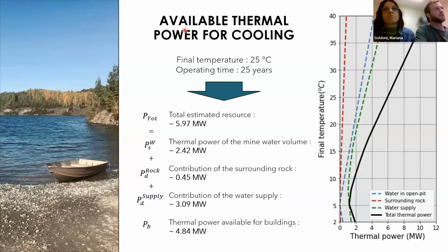Finally, for the available thermal power for cooling, assuming a final temperature of 25 degrees Celsius and an operating time of 25 years, I estimate a resource around 6 megawatts. Considering the energy consumed by the compressor of the geothermal heat pump, the thermal power available for buildings could be around 4.84 megawatts. This is the end of my part. I'll hand over to Mariana.